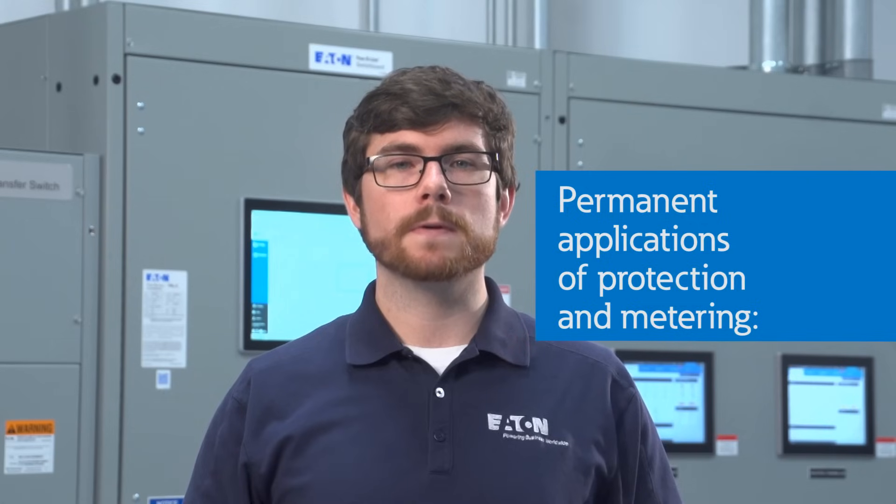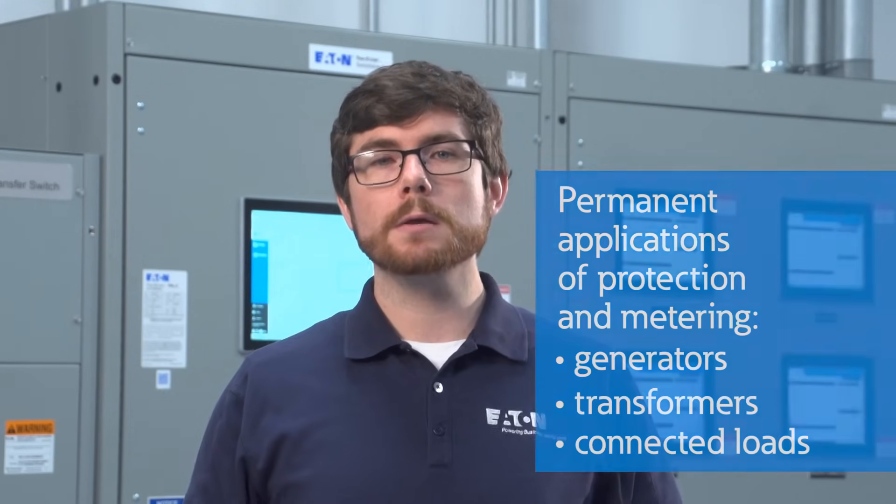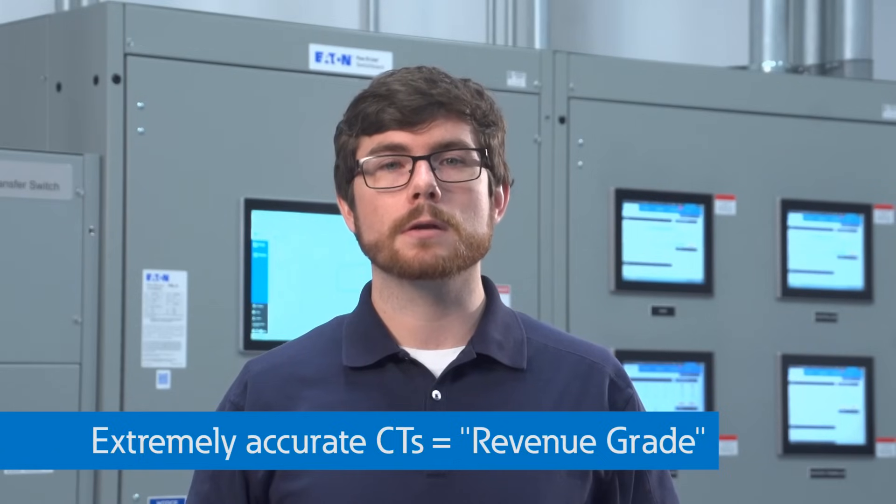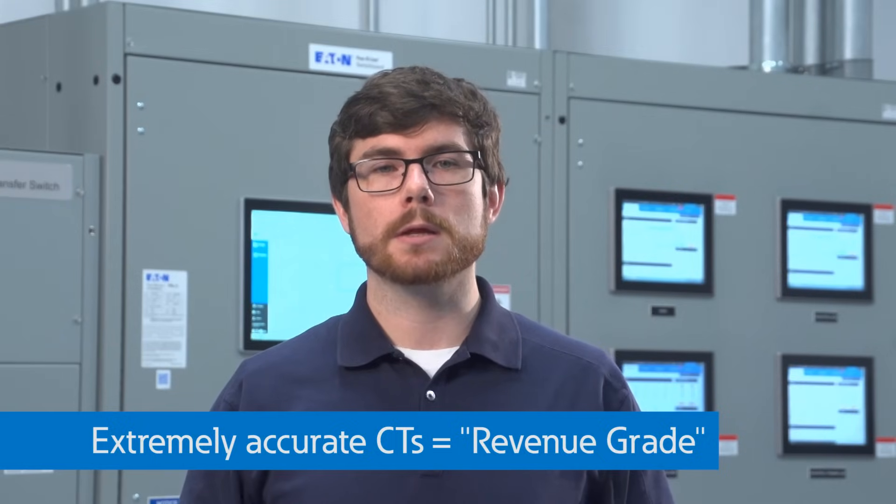For permanent applications of protection and metering, CTs can be found anywhere from generators to transformers to connected loads or anywhere we want to monitor current flowing in the system. For example, utilities use CTs at their customer's incoming service to monitor the current and power usage for billing purposes. These CTs must be extremely accurate and are considered revenue-grade since they are used for billing.